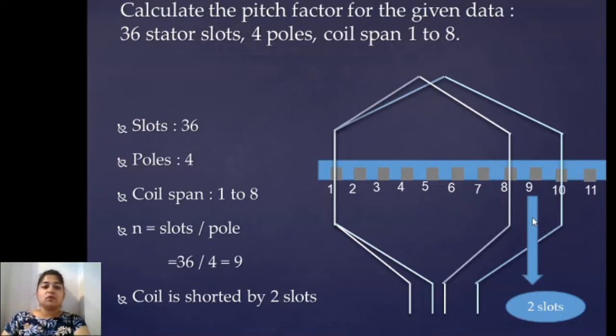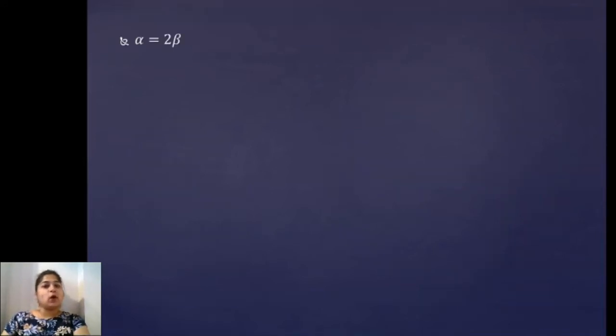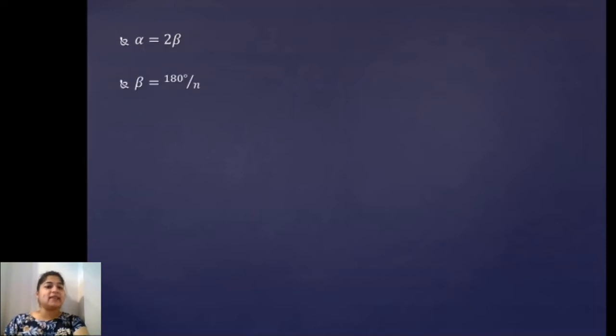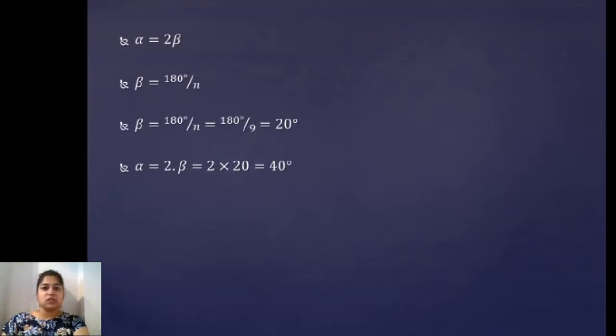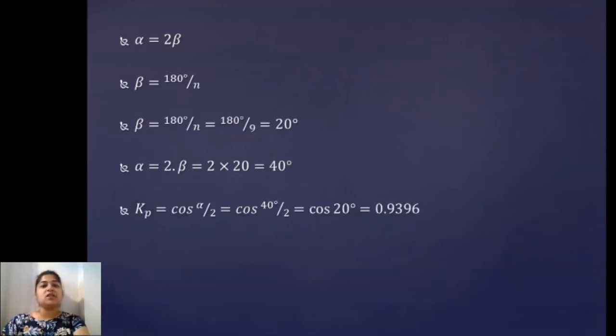Since the coil is shorted by two slots, alpha will be twice beta, where beta is 180 divided by N and N is slots per pole which we got as 9. Substituting, beta equals 20 degrees. Substituting in the alpha equation, alpha equals twice beta which is 40 degrees. Now substituting in the kp equation — kp equals cosine of alpha by 2 — we get kp equals 0.9396.